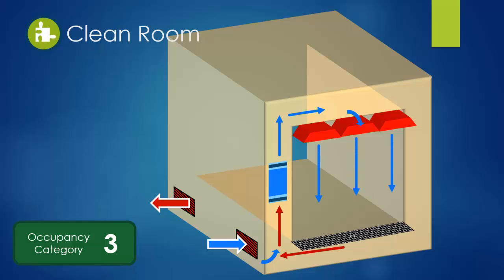Once filtered, it is introduced into the clean room at the ceiling, which will direct the air in a unidirectional flow. The air will then flow through grates in the floor, and the required amount of air will be returned to the adjacent R&D space. To serve the internal loads in the space, a heat pump is located within the fan-filtered boxes.